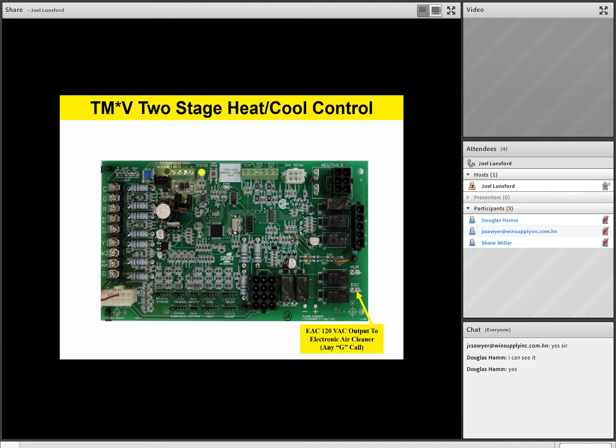At the bottom of this board, in the lower right-hand corner, you're going to notice that your flame current pad is down below on this board. And again, that flame current will be 1 microamp is equal to 1 volt DC. And the technician will just have to use his normal voltmeter to find flame current on this board as well.